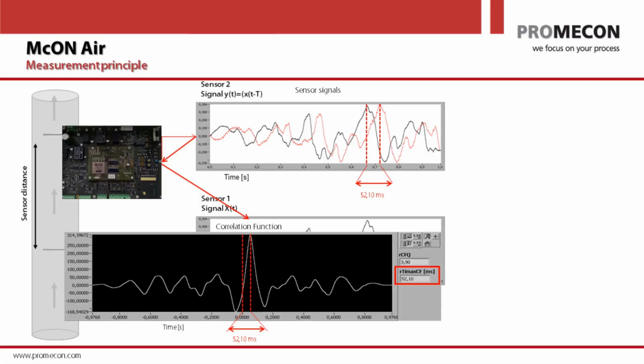This is very, very fundamental because that is your drift-free measurement. There you have it. Every second, our system will give you a time shift. If you now take the distance of the sensor and divide it by the time shift, you get a velocity. You get feet per second. And if you now multiply with the cross-sectional area of your duct, you will get cubic feet per second or cubic feet per minute. You already have your actual flow.